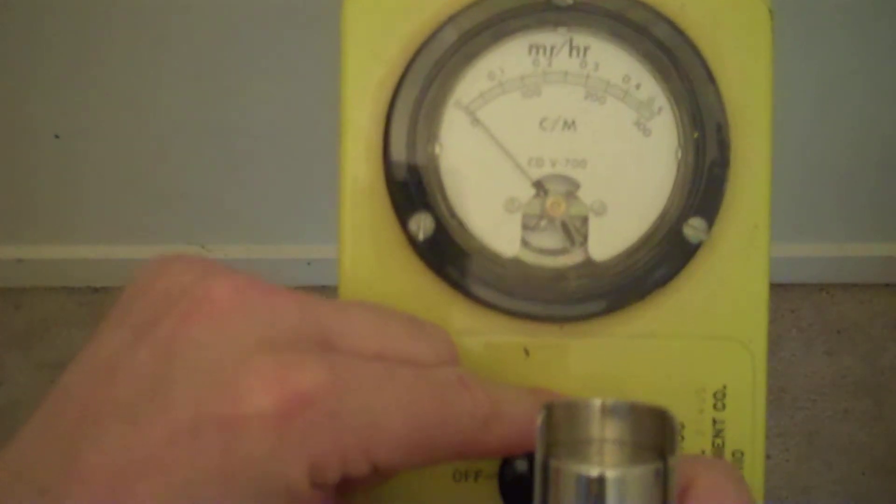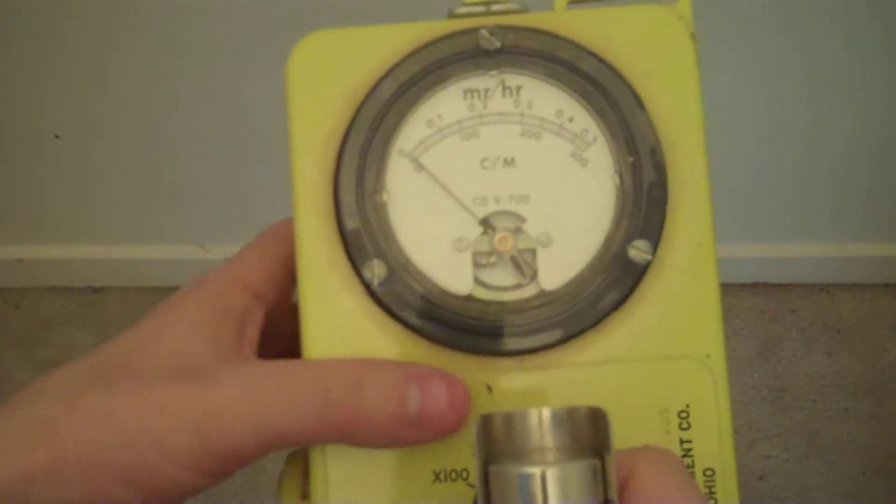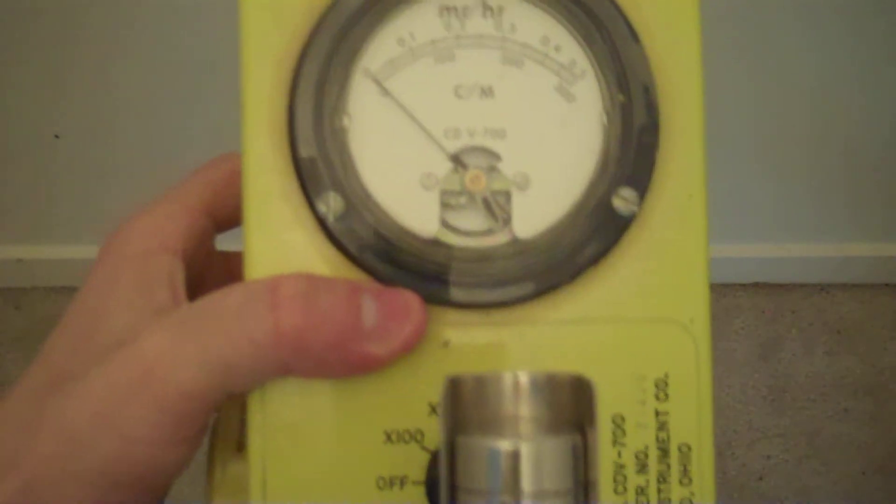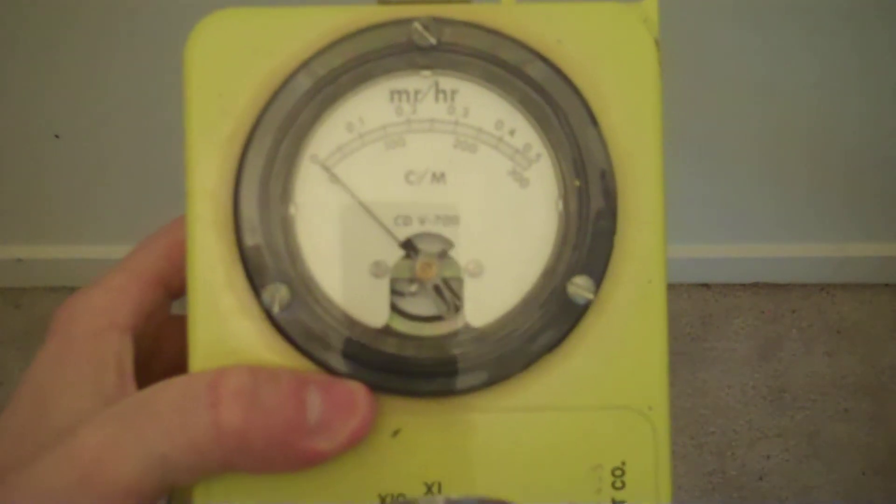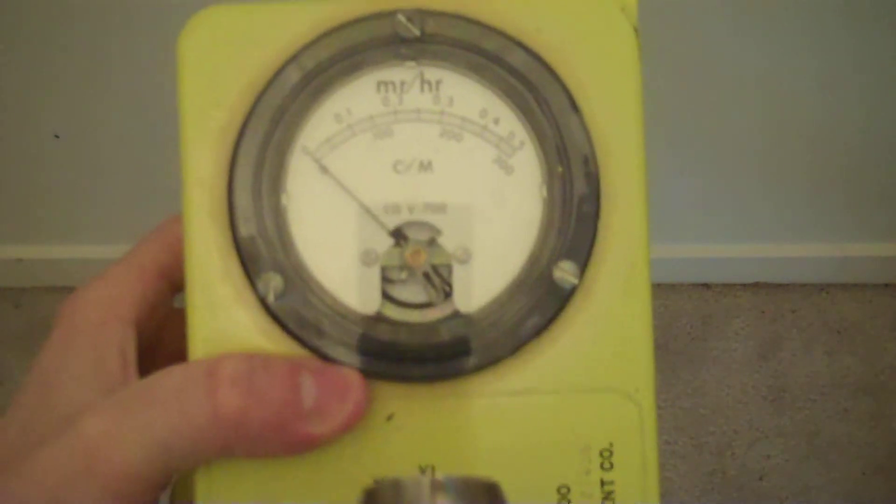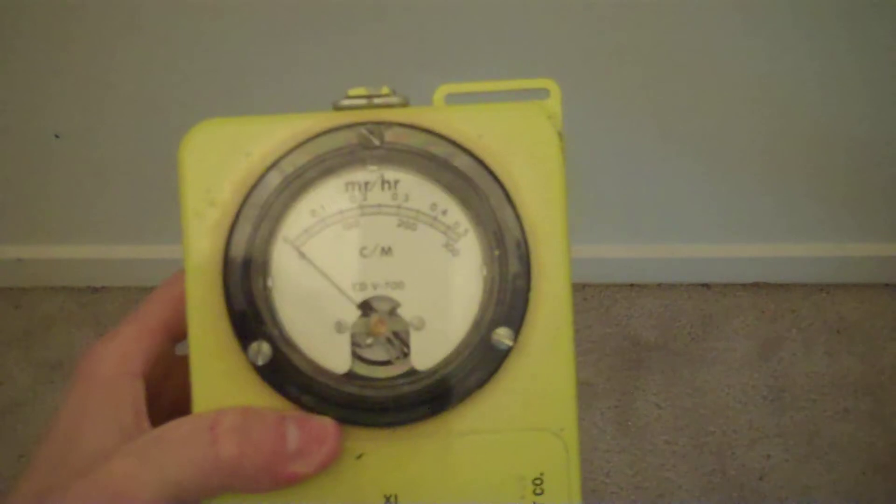In the times 10 mode, the scale is now multiplied by 10. Whereas it was 100 counts per minute, it is now 1,000, and so on. So the range is now 0 to 5,000 counts per minute, or 0 to 5 milliroentgens per hour.